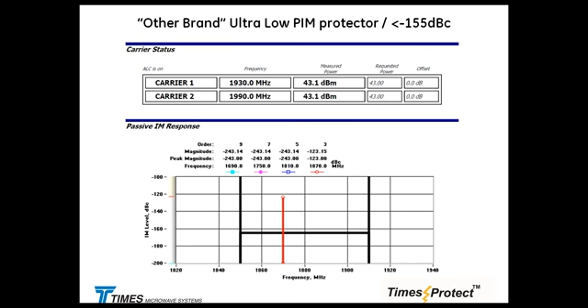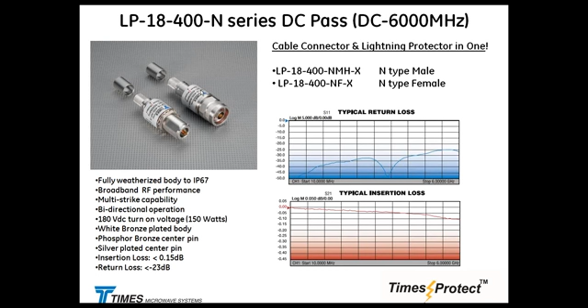Here is an example of how to minimize the number of connectors. Here is a device going up to 6 gig. It's a basic gas tube, bidirectional, and it can be crimped directly at the end of the cable using the same CST 400 tools for the LMR 400. So you basically eliminate 2 connectors for the protector, crimping it right at the end of the coax cable, and there you go.